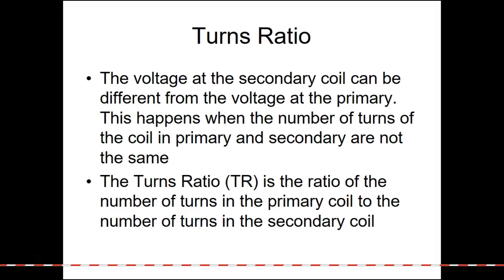They guarantee, Alabama Power guarantees plus or minus 10%. So it could be 10% high or 10% low, because all their regulation is done at the power plant. And some of your substations have the ability to electronically vary the number of windings in the secondary to help regulate the voltage on the other side. But it depends on how close you are to a substation.